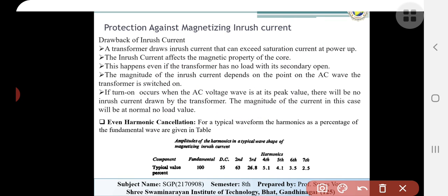Okay, these are the basic introductions of the harmonics. Here you can see that we can put a table for the basic amplitude of the harmonics in the typical wave shape of the magnetizing inrush current. Generally, the fundamental is 100, then DC is 55. Then you can see the first peak spike and the typical value of the percentage is 63. Then the second you can see 26, 5.1, 4.1, 3.5 and 2.5. So these are the odd and even harmonics that will affect our transformers.